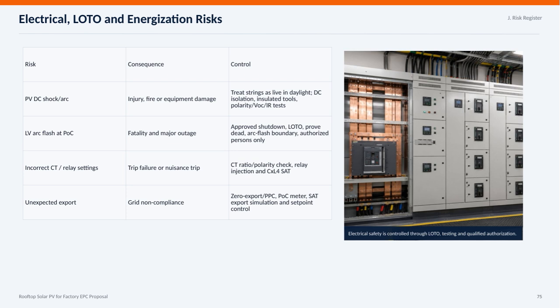Controls include using zero export or power plant controller strategies, installing a point of connection meter, carrying out site acceptance tests with export simulation, and closely managing set-point controls. Overall, electrical safety is rigorously maintained through disciplined lockout-tagout procedures, comprehensive testing, and ensuring only qualified personnel perform critical tasks.